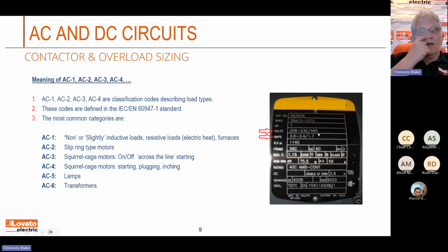208-230-460. Okay, and a lot of our stuff, we need to know which one is it? Is it 208? Is it 230? Is it 460? Some companies have dual ranges on their contactors, but we don't, because you see the big amp difference in there. If it's 460, you're half the amperage, so you're going to use a lot smaller contactor. Okay, those are just some of the things we look for in a motor.